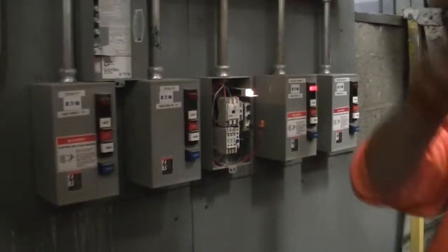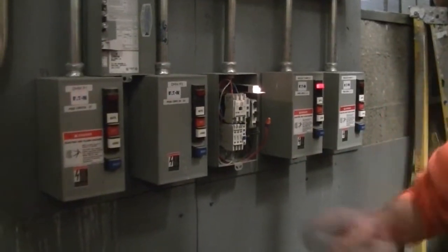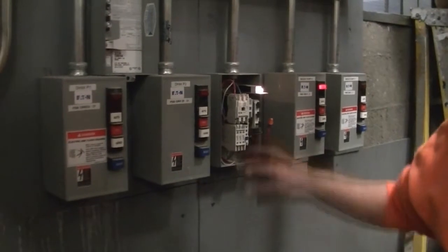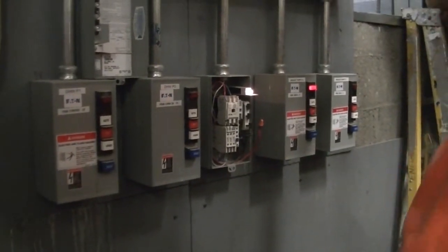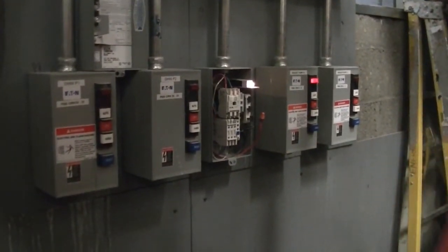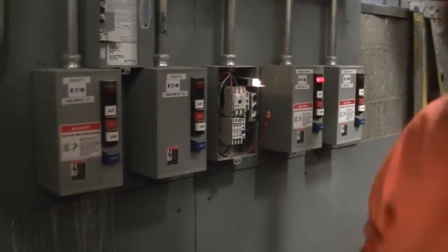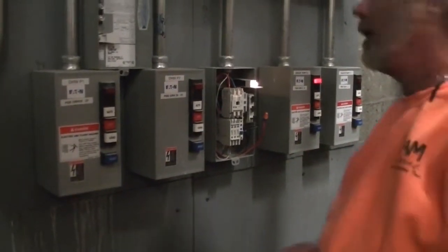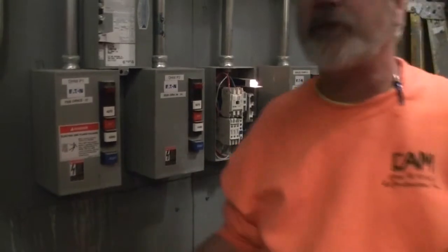The pump breaker is for protection of the pump. Control power for the starter comes from the boiler. That's important to know. Does it say that on there? Does it say 2 sources of power? No, it doesn't. It's the same thing as having a transformer in a building that does all your controls, but your appliance still has its own power. It's the same premise of design. Okay.